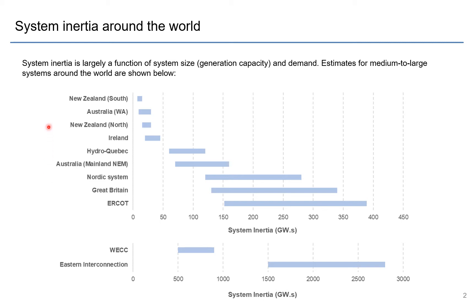On the small end of the scale — less than about 50 gigawatt seconds — we have systems like the two New Zealand systems (North and South Island), which are interconnected by an HVDC interconnector, the West Australian system, and Ireland. These are all small island systems. As you get bigger, you have Hydro-Quebec in Canada, the eastern Australian system, and the Nordic, Great Britain, and ERCOT systems in Texas. Off the scale are the western and eastern interconnections in the US, at 500–1,000 and 1,500–2,800 gigawatt seconds respectively.